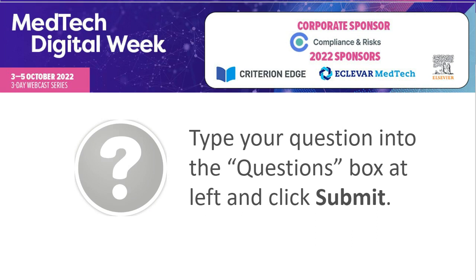How you get them is sometimes a different question. Where do they come from? Where do acceptance criteria come from? They come out of the state-of-the-art section, because acceptance criteria are derived from data, actual data, that is extracted from your competitor device search. So if you have identified your safety and performance objectives, you know, rate of bleeding, periprocedural bleeding, survival at 30 days, very quantifiable types of safety and performance objectives, then you must find the answers to those data points in your competitor list, your competitor search.